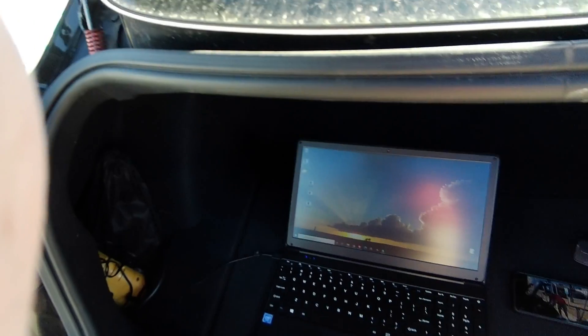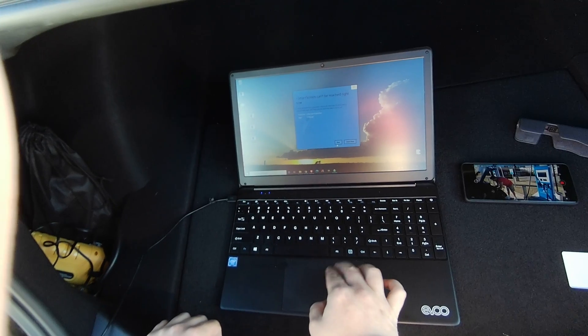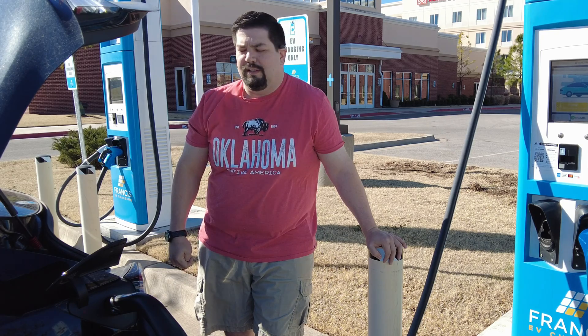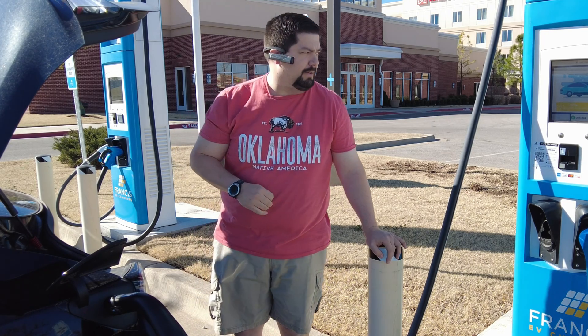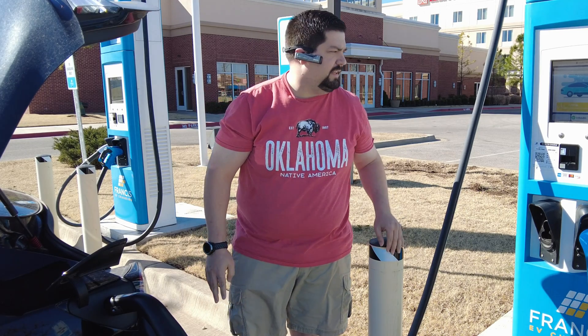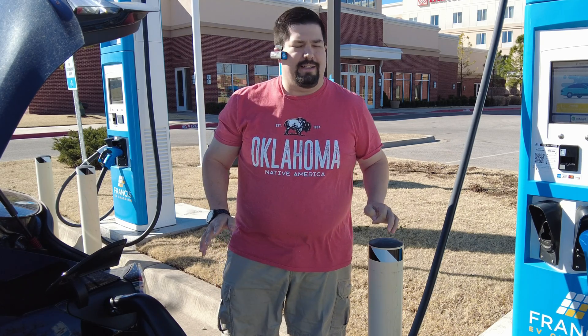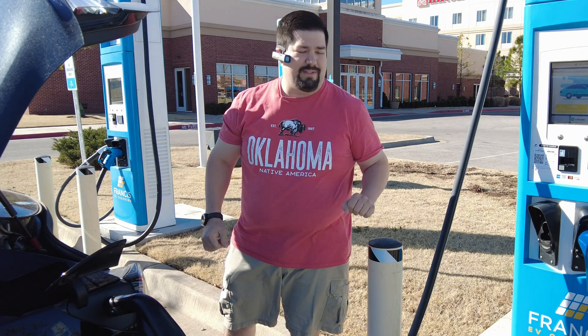What I'm going to do is install firmware 139 and see if it changes anything. So far here's where we're at: I've tested three times, it's worked every time and started charging. The first time I got full power, the second two times it capped at 24 kW. I'm loading firmware 139 just to see if it changes the charge profile. There's another station down there I can try out too. Still got some trial and error to do - let's keep positive thoughts. I'm already a lot farther than I've been in the last videos - at least it's charging.